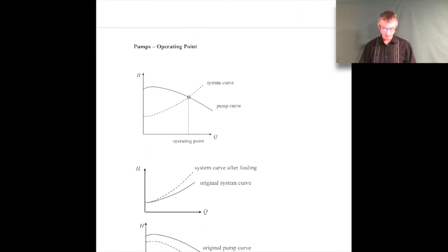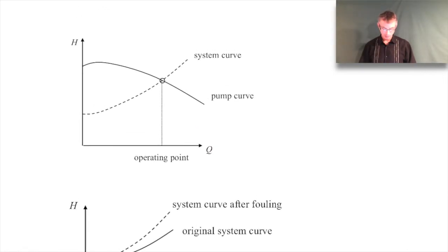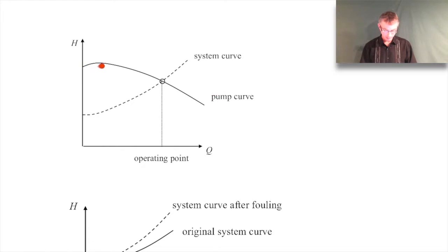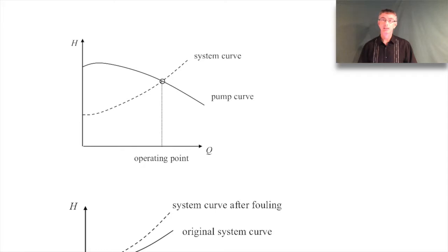So what we're going to talk about today is finding the operating point for a pump in a pipe system - it's a pretty straightforward topic. What we'll do is focus on the pump performance curves - this kind of head rise as a function of flow rate. You're very familiar with the pump curve here, that's this black line, kind of an upside-down quadratic looking equation. And then we have the system curve, which is this dashed line. The system curve is a property of the system; the pump curve is a property of the pump and you get it from the manufacturer. The system curve comes from the extended Bernoulli equation.